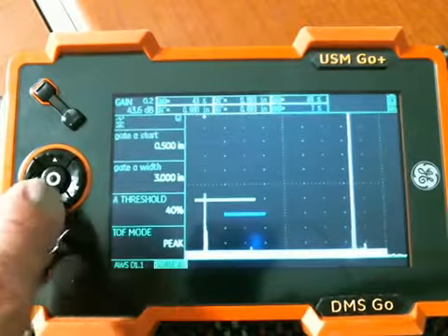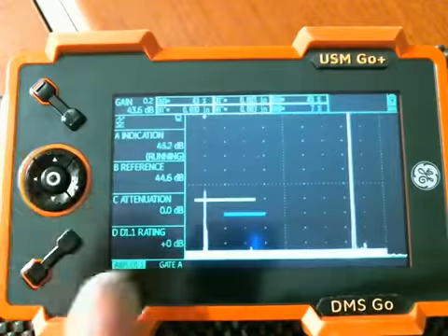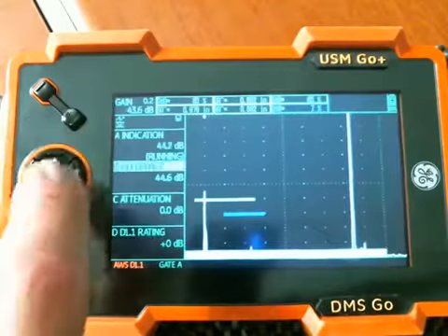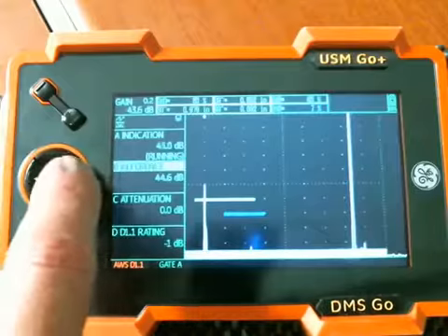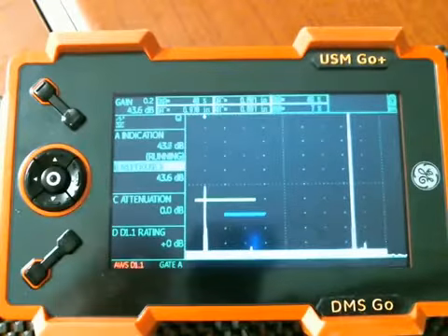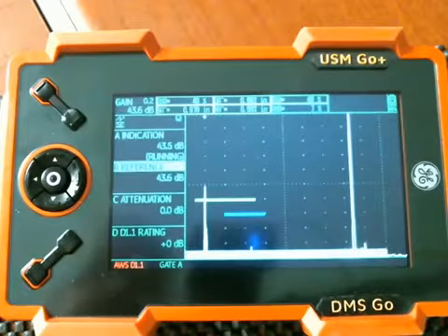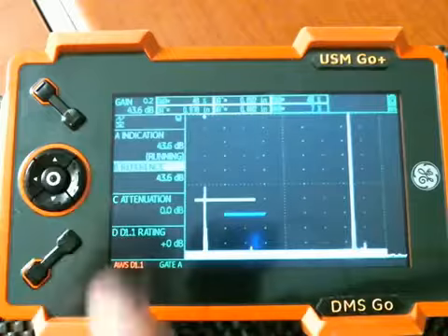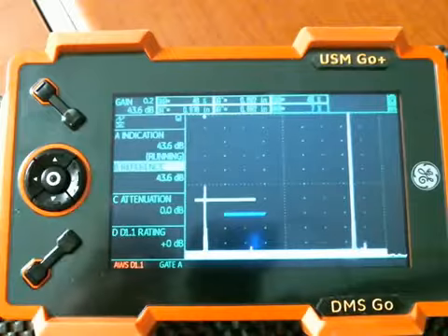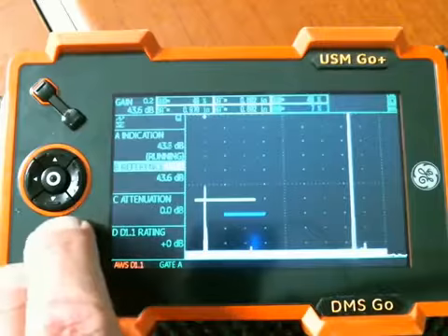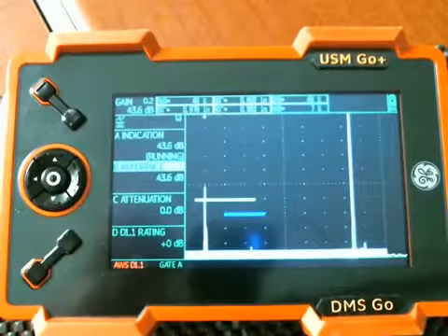Okay, now that I've got the gate set up, go back to AWS D1.1, go up to the B reference, peak up again, and record the reference. And you'll notice because I already had a reference programmed in from a previous run, when I did the right click to input the reference, it asked me to confirm that with a double key press. That means press these two ends of the rocker switch, press both at one time.